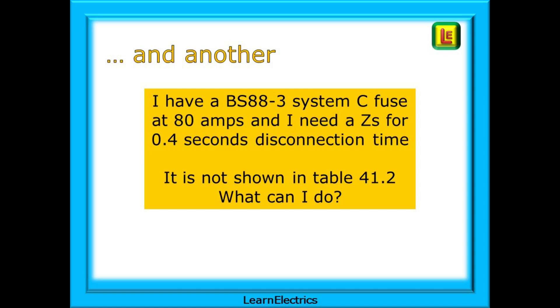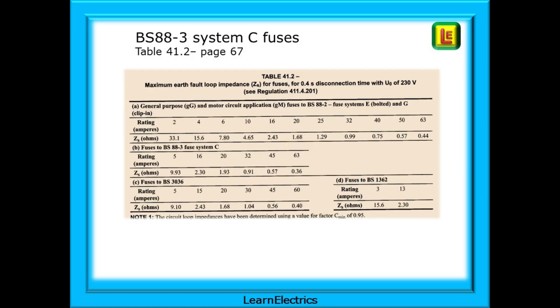Well, let's start by looking at this one. Look in the Brown regs book, and on page 67, you will find table 41.2. This table shows the tabulated ZS or earth fault loop impedance values for fuses that are required to disconnect in 0.4 seconds or less. If we look for BS88-3 system C fuses about halfway down the table, we see that the data stops at 63 amps. An 80 amp fuse does not exist on this table. So, what would the ZS be if we wanted it to operate in less than 0.4 seconds? And notice that the other fuses listed do not go past 63 amps either. Yet we know that bigger sizes are available. What can we do?